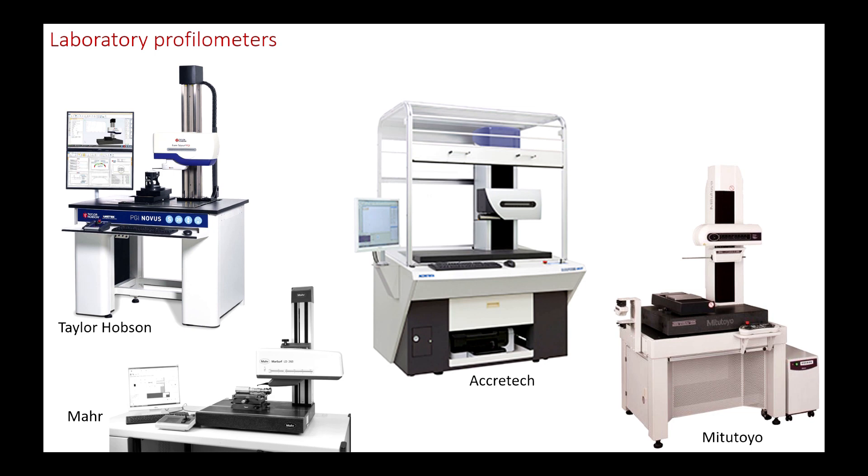Laboratory profilometers allow more precise measurements, including not only roughness but also waviness and form deviations. More and more profilometers do both surface texture and contour. The high precision of these devices requires them to be isolated from environmental disturbances, mechanical and acoustic vibrations. This is why some models are mounted on active damping tables and are protected by closed enclosures.